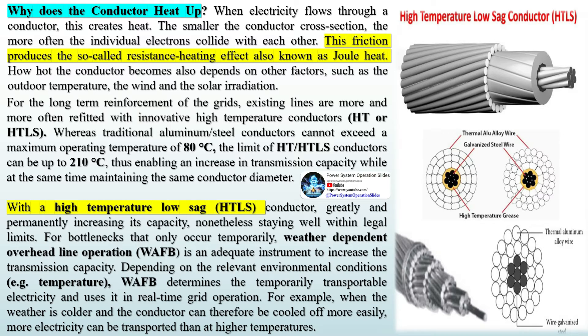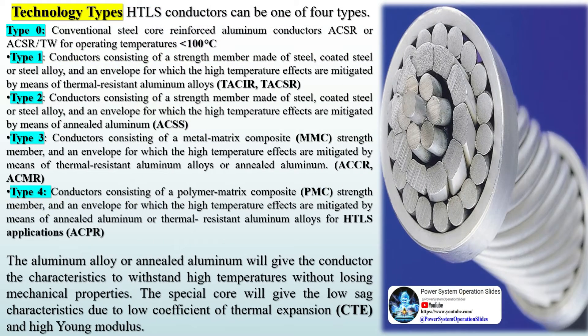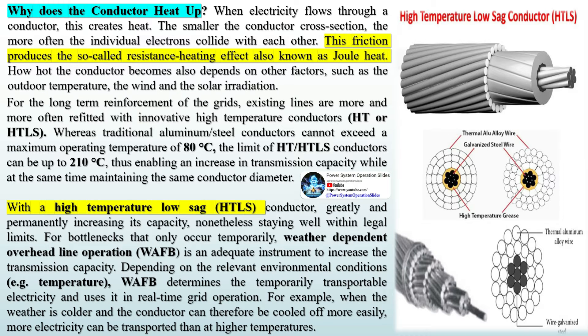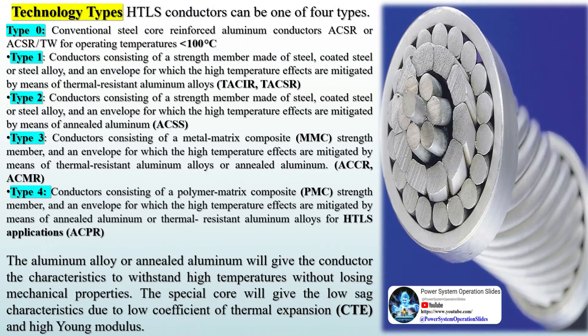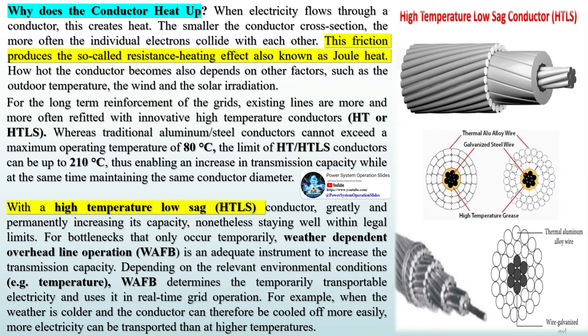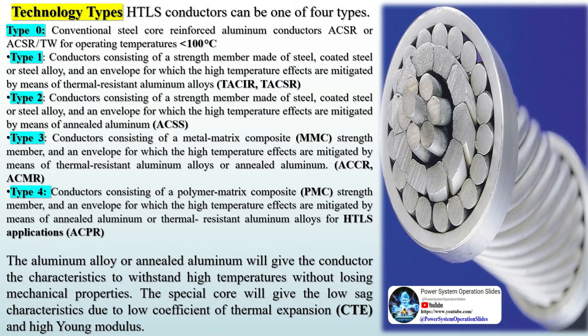Whereas traditional aluminum steel conductors cannot exceed a maximum operating temperature of 80°C, the limit of HT or HTLS conductors can be up to 210°C, enabling an increase in transmission capacity while maintaining the same conductor diameter. With a high-temperature low-sag HTLS conductor, capacity can be greatly and permanently increased whilst staying well within legal limits. For bottlenecks that only occur temporarily, weather-dependent overhead line operation (WAFB) is an adequate instrument to increase transmission capacity. Depending on environmental conditions such as temperature, WAFB determines the temporarily transportable electricity and uses it in real-time grid operation. When the weather is colder and the conductor can be cooled off more easily, more electricity can be transported than at higher temperatures.